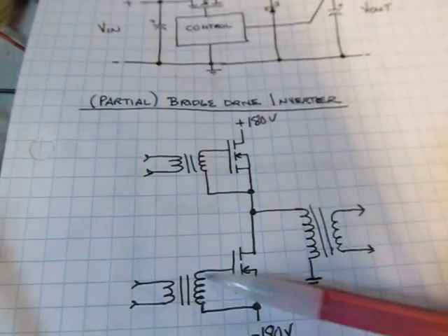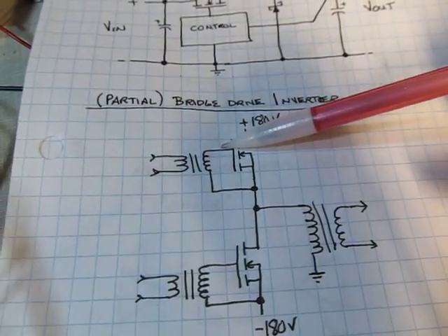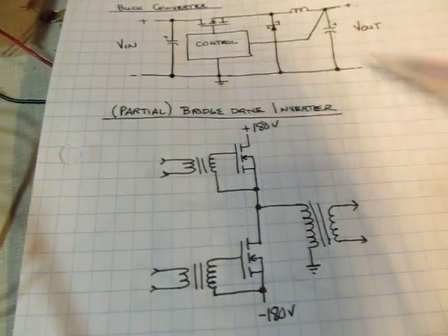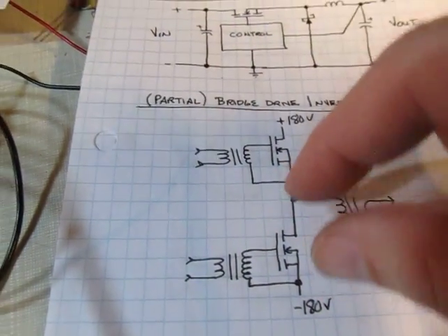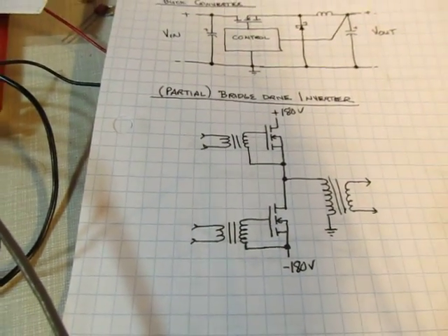We may also have, like here's a half bridge driver and an inverter. In this situation, I might want to measure the turn on voltage, the gate to source voltage here. And that voltage difference may be just a couple of volts. But those voltages, any one of them in this case could be anywhere between 180 and minus 180 volts depending on which device is on. So that common mode voltage we don't want to see, but the difference voltage between them we do. So the differential probe would work in that application.